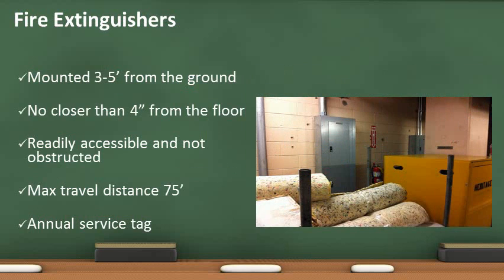Extinguishers are to be mounted 3 to 5 feet above the finished floor, with 3 feet circumference of clear space. The annual service tag shall be attached, and the extinguisher visually inspected monthly by on-site staff.